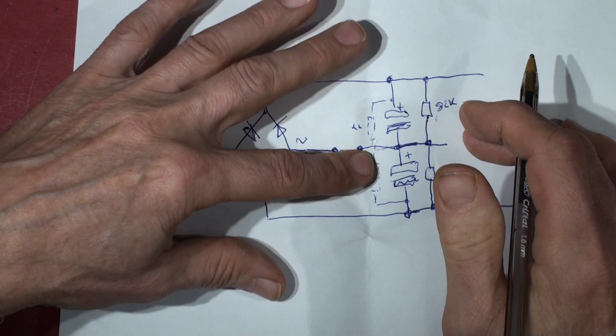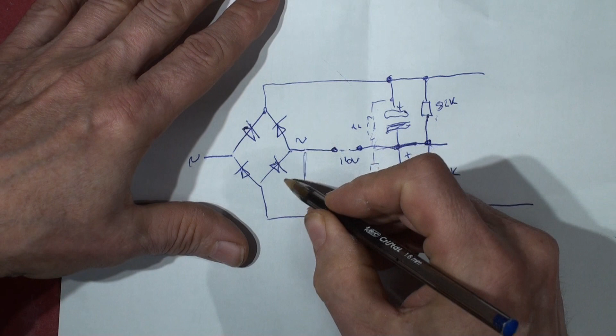And if they're not in whack, then when you turn the power up to full voltage, one might drift above its voltage rating and damage the capacitor. So always check them, because it will be a source of grief if you don't make sure these capacitors aren't leaking or there's something else pulling the voltage around.